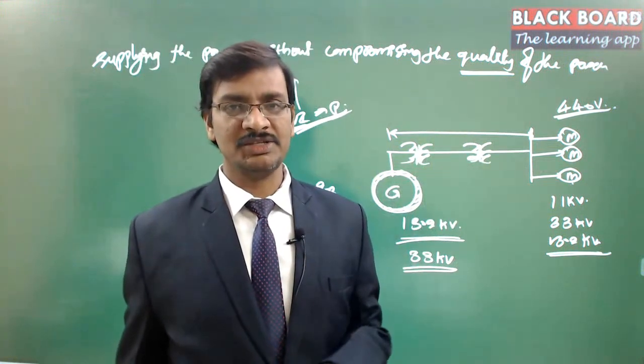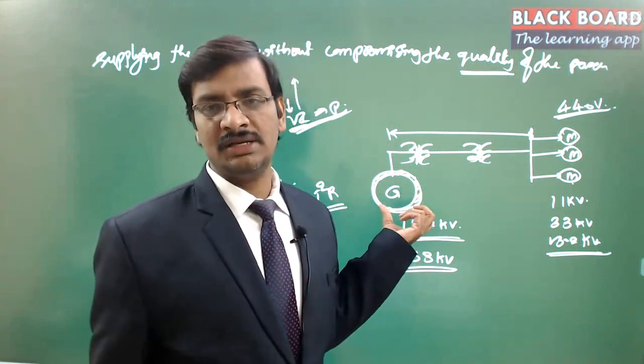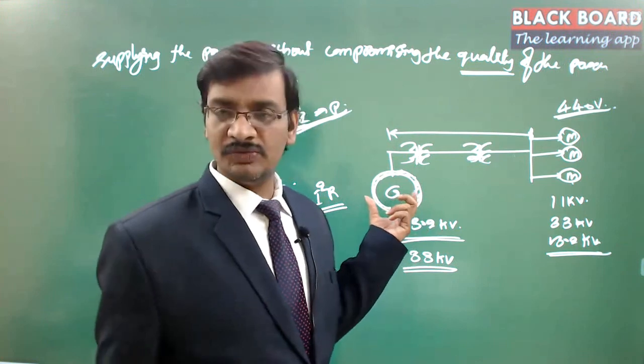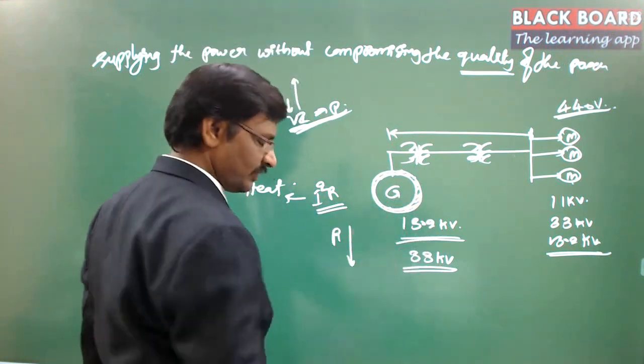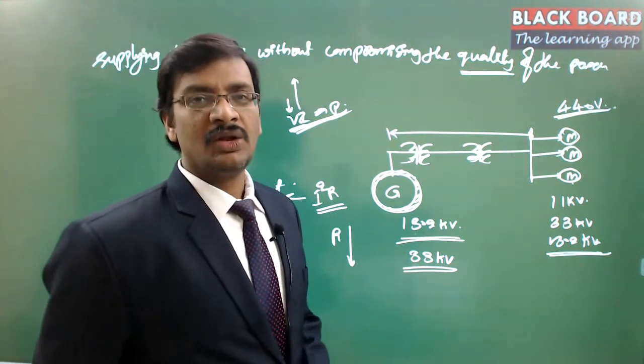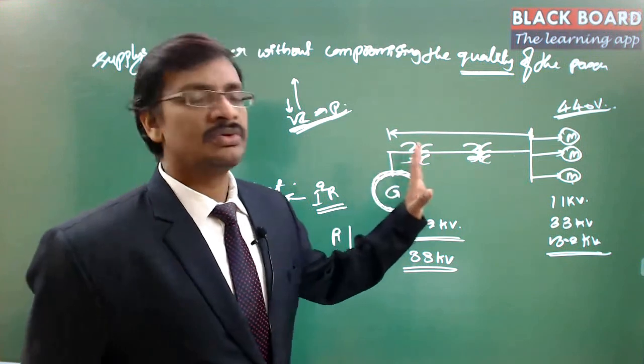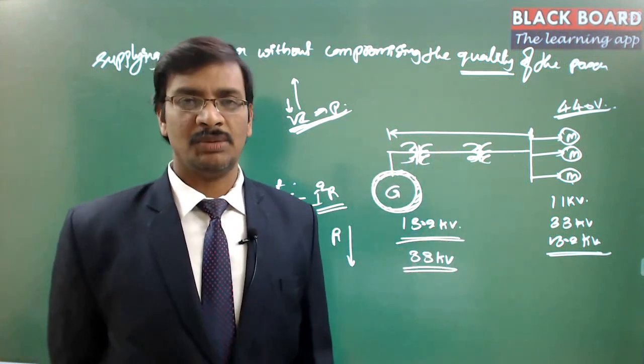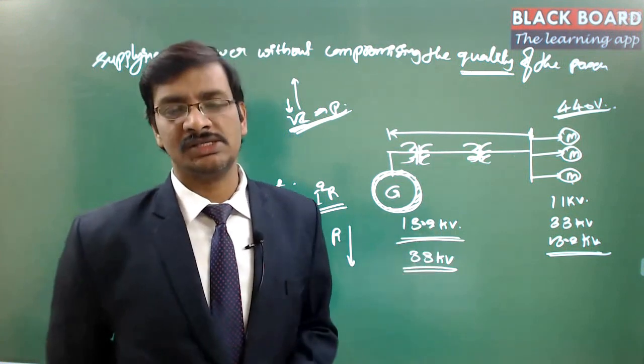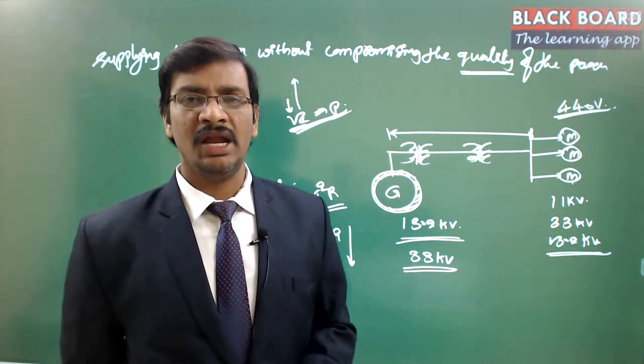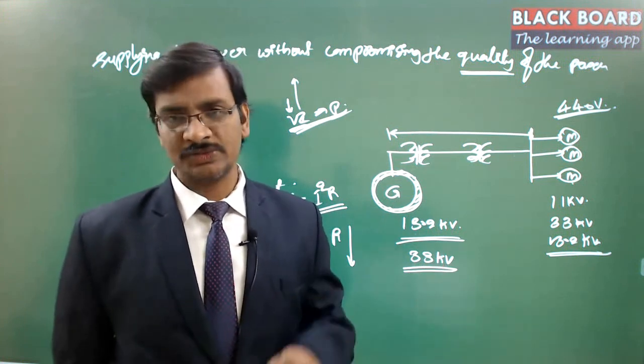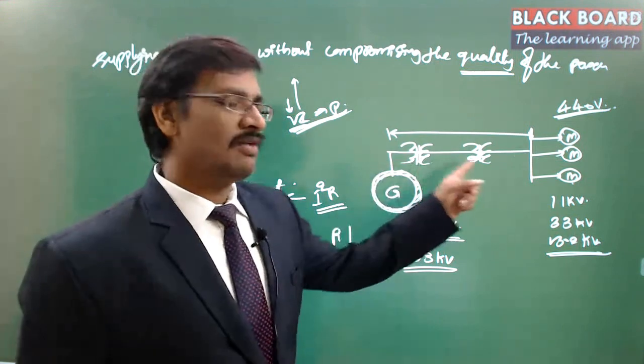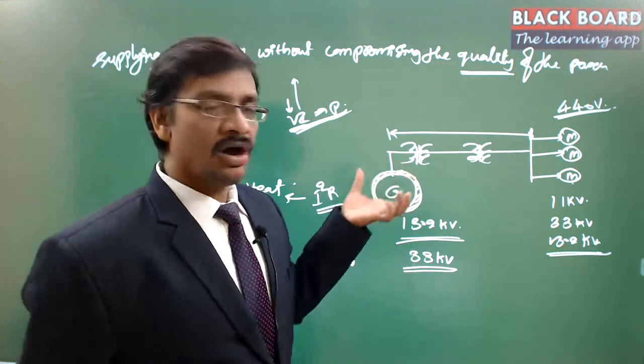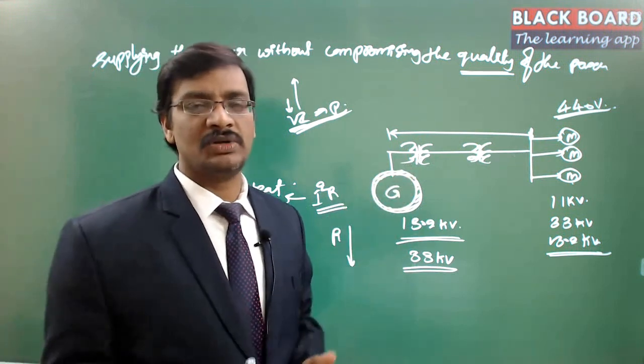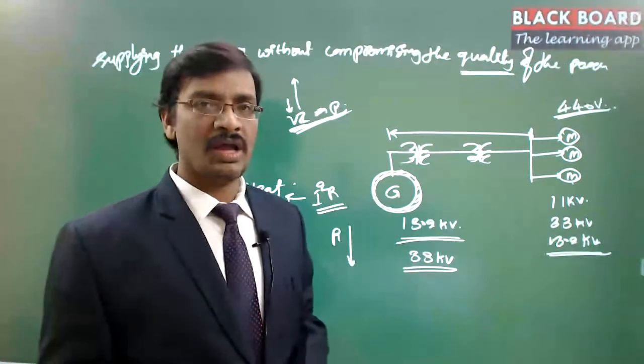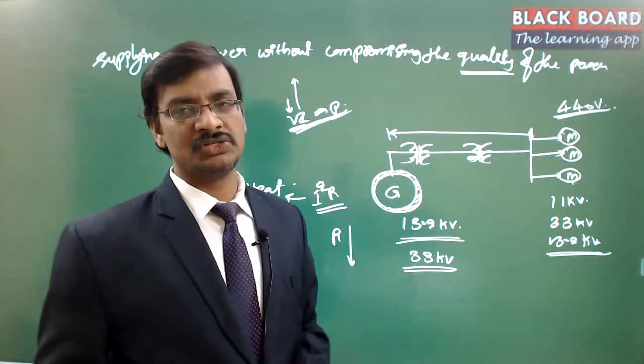What kind of issue it will create in the transmission line is, here we have copper conductors. If you keep copper conductors with a higher area of cross section, the resistance value is going to be usually less, because it is a copper material and the area of cross section is more. Now the same kind of copper material we cannot use to transfer the power for 100 kilometers, because the power which is generated in one state will be supplied even to other states as well. The distance between two different states will be at least more than 200-300 kilometers. To transfer the power from one location to another, we cannot have a copper line, which is a very costly affair, because a copper line, that too 3-phase lines, 3 parallel lines, has to travel for 300 kilometers, and to have a higher capacity of current, you need to increase the area of cross section very, very high.